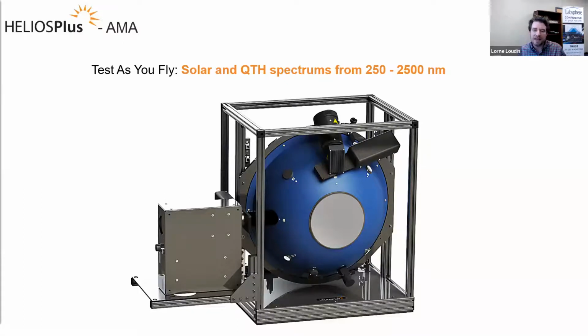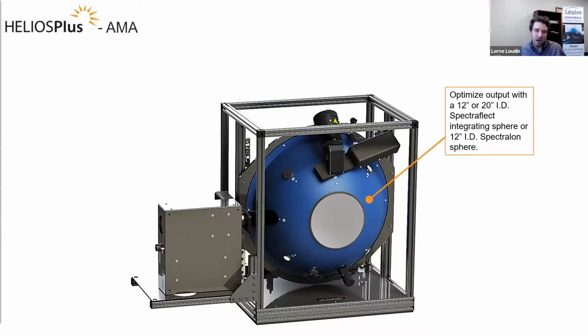The Helios Plus AMA family, the A family systems, are the ultimate expression of uniform calibration source technology, allowing you to test with spectrums and levels that are equivalent to solar outputs. So you can optimize your system, and this is true for most systems. You actually have more options in some of the other Helios Plus families. You can optimize your A family with either a 12-inch or 20-inch SpectraFlect sphere or a 12-inch Spectralon sphere.